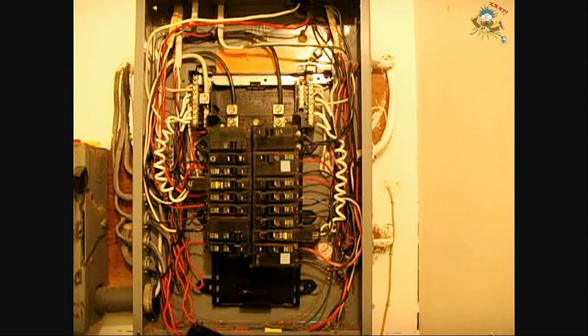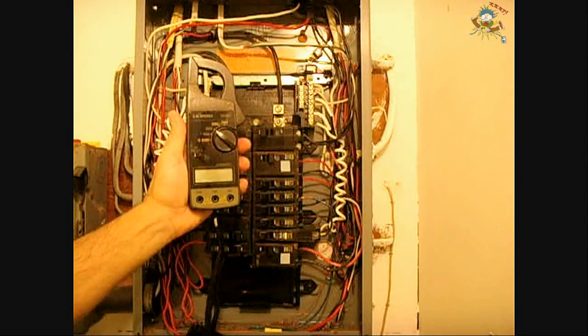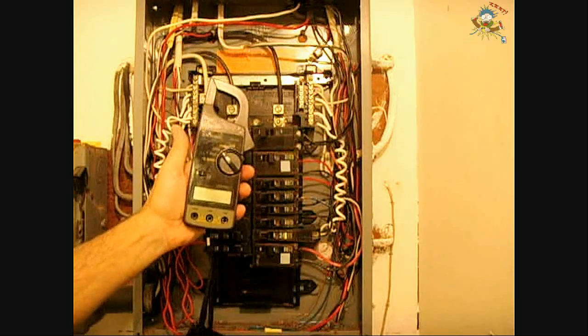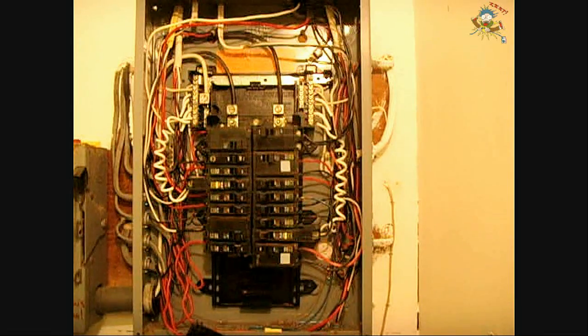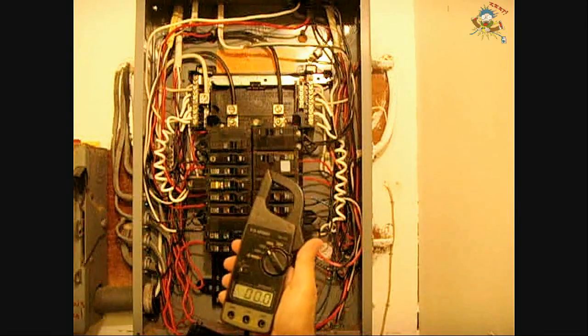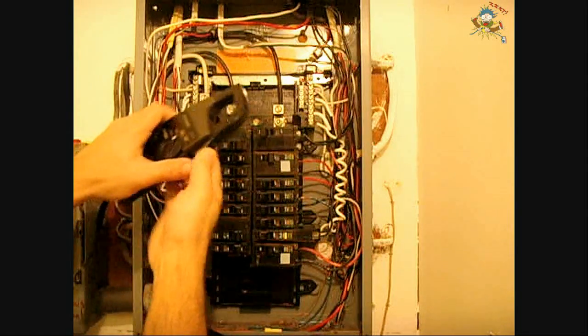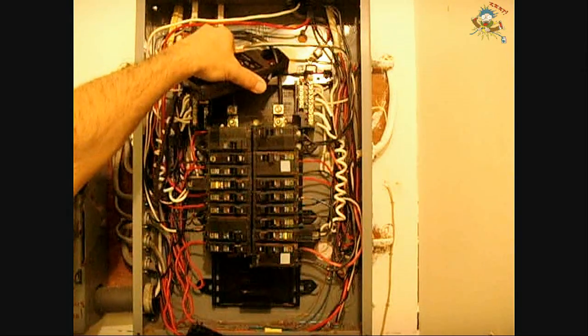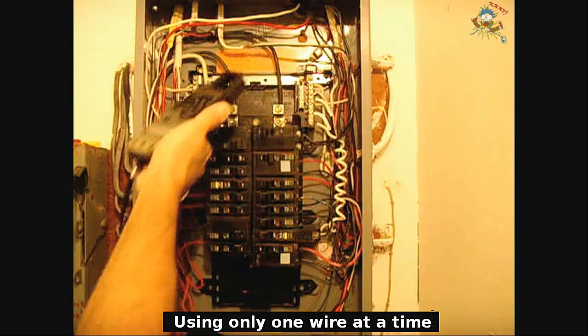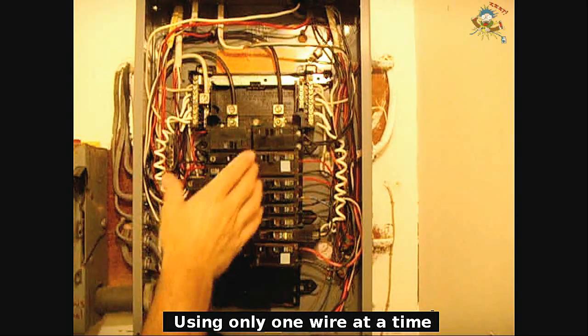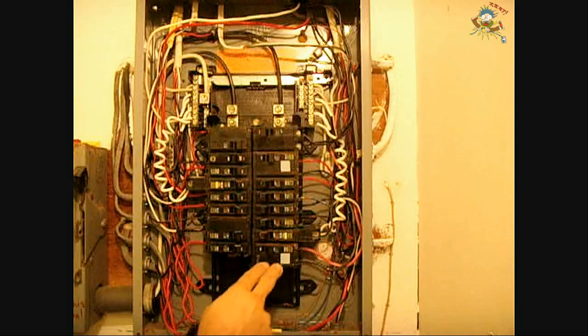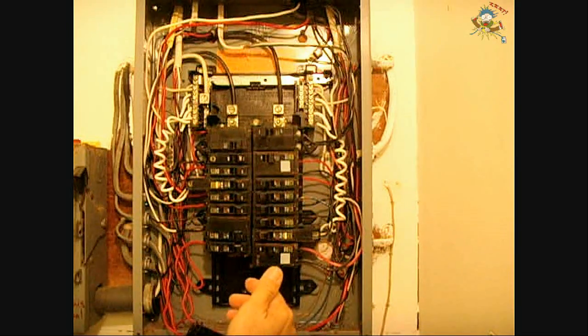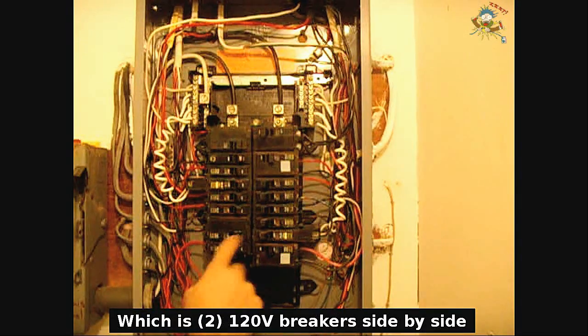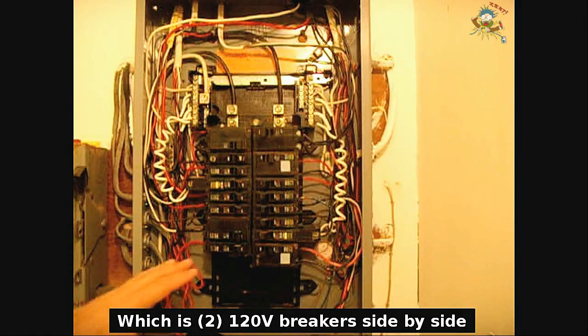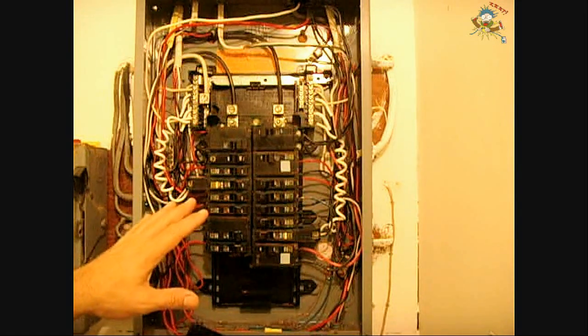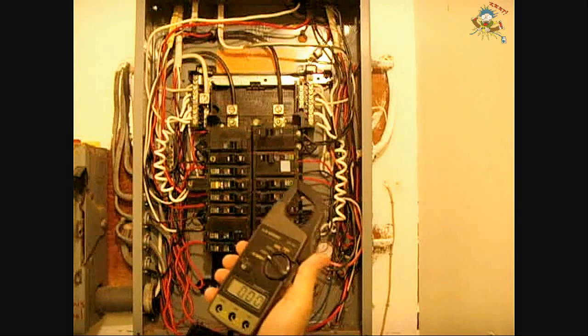Another useful tool is a clamp-on meter for measuring current. This goes up to 600 amps. And what this is good for, I would turn that on. This clamps right around your wire, like that, and then you'll be able to measure how much current is flowing through the wires. When you set up a breaker panel like this, you put all your 240 volt breakers in. Those are fine. When you put in your 120 volt breakers, you want to make sure that you have a balanced load on the panel, and that's where this would come in very handy.